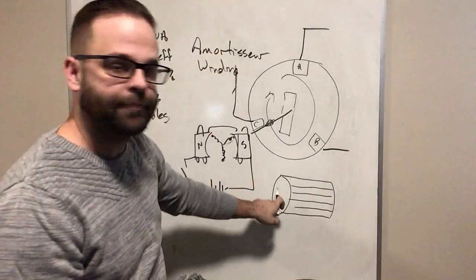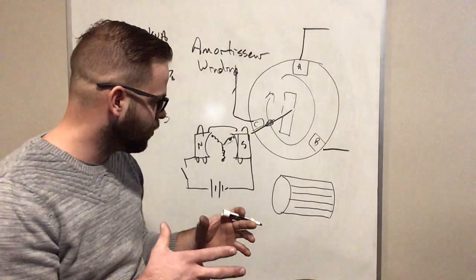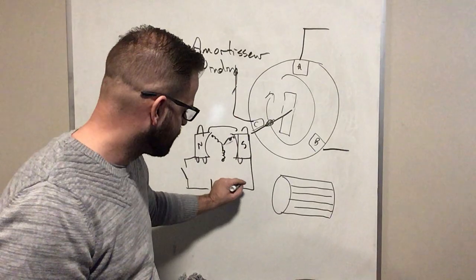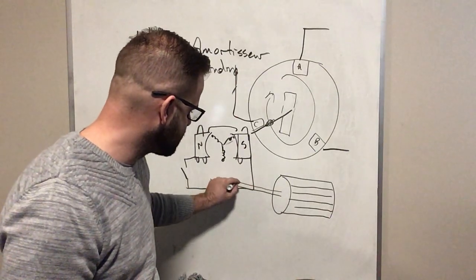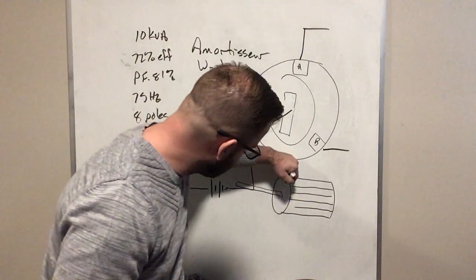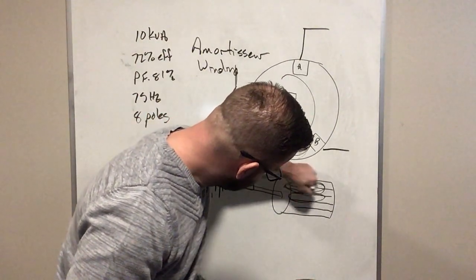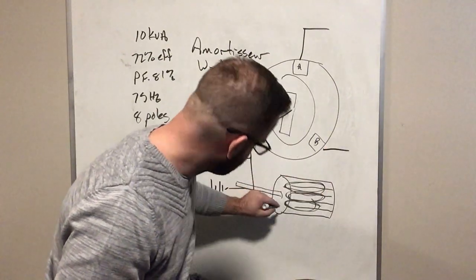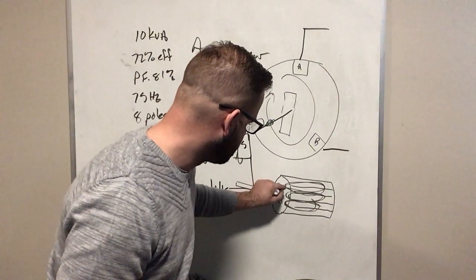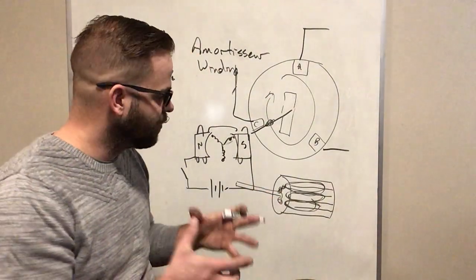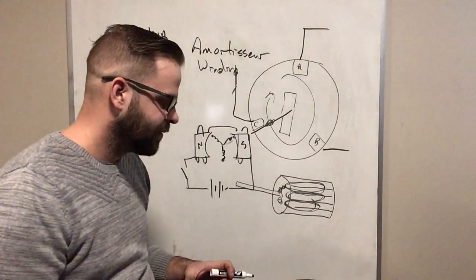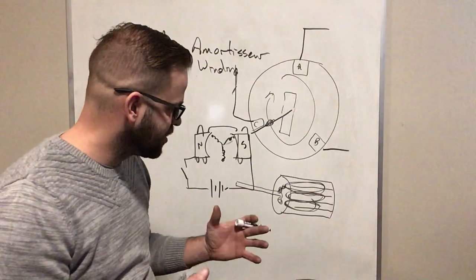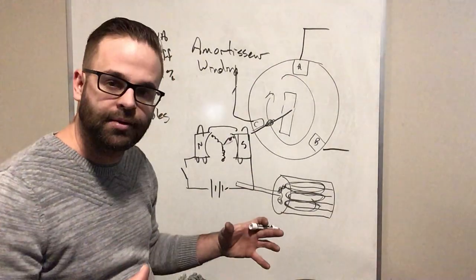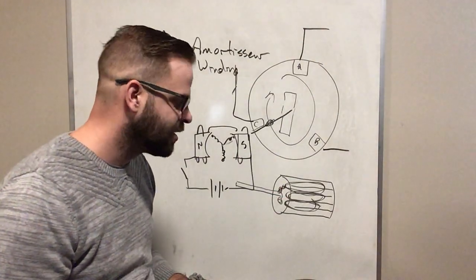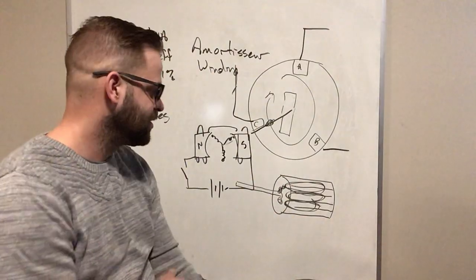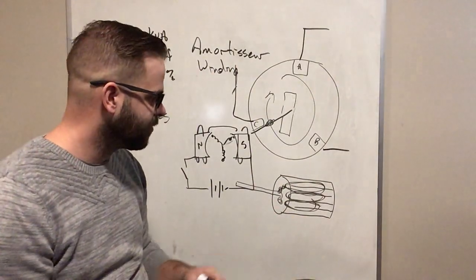And that amortisseur winding is around those salient poles. So the shaft of my motor would come around, this would be my shaft, and I'd have all of my three-phase windings all inside here, creating poles all the way around the outside of that rotor, and that amortisseur winding would be around it. That amortisseur winding is either copper, aluminum, or steel bars, thin bars that go around all of the coils, and it's got solid rings on both sides, and those solid rings complete a path for current to flow.